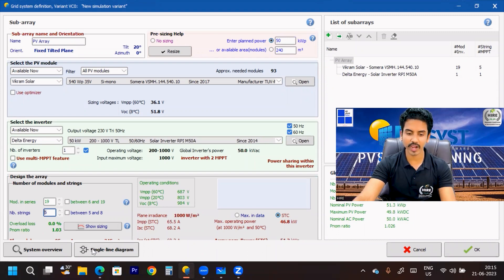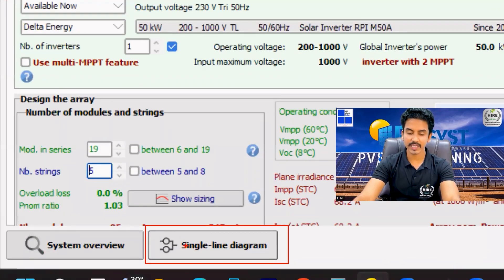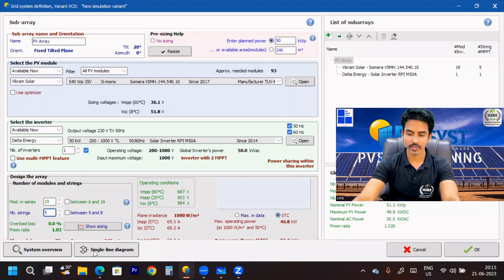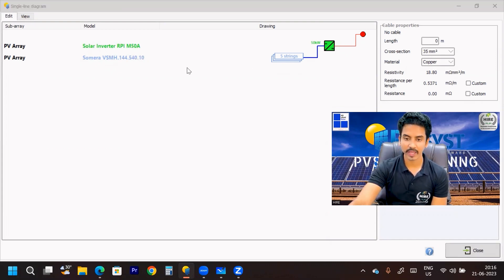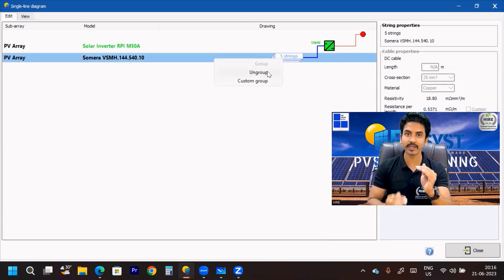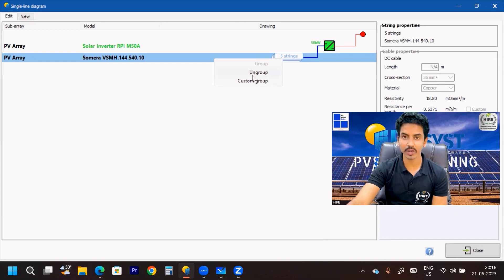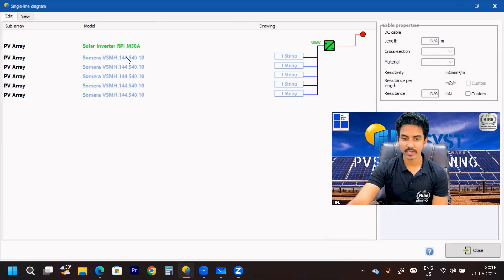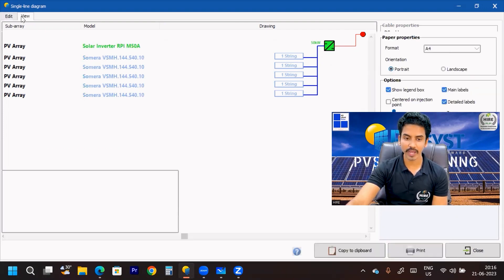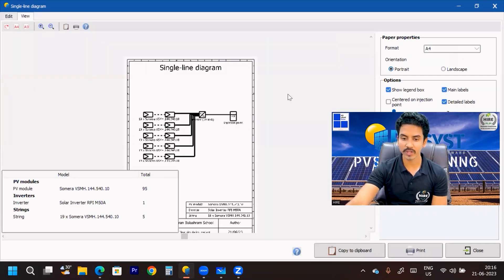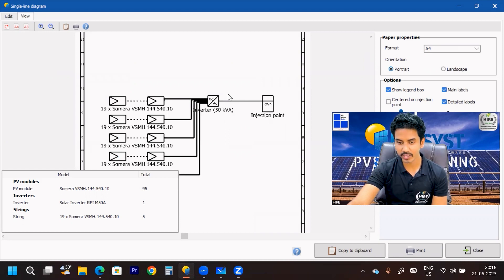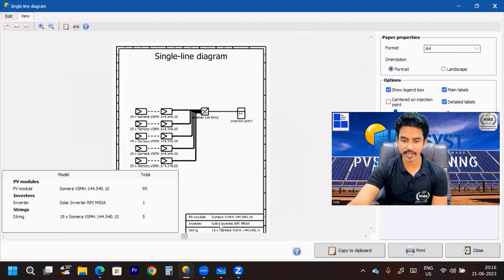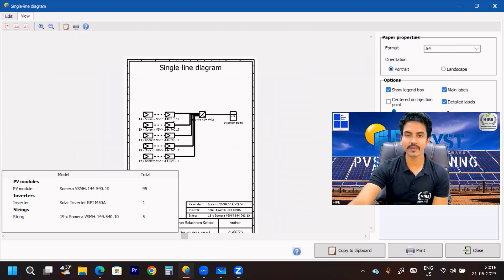You can find one option here: 'Single Line Diagram', shown after your system overview. When you click on Single Line Diagram, it shows how many strings you have and how the inverter will be connected. If you want to show the strings separately, right-click and click 'Ungroup' — it will display string-by-string. Go to the View option and the diagram is shown with injection point, inverter capacity, and string count all mentioned.